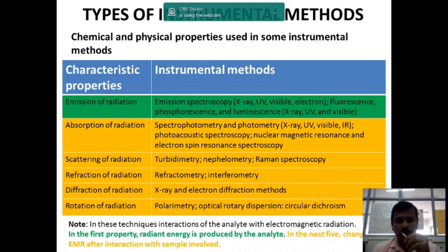So by using a photometer or spectrophotometer, you need a lamp, a source that could provide radiation belonging to the visible region, white light radiation, wavelength 400 to 800 nanometer with respect to UV or visible region. You need a tungsten lamp. A tungsten lamp is going to be the stimulus.